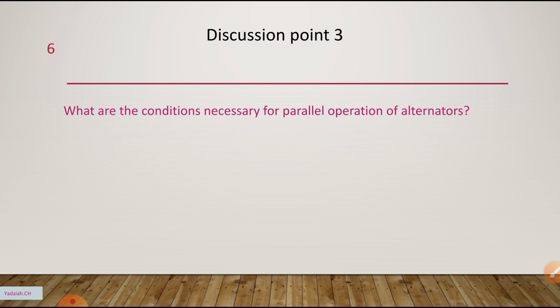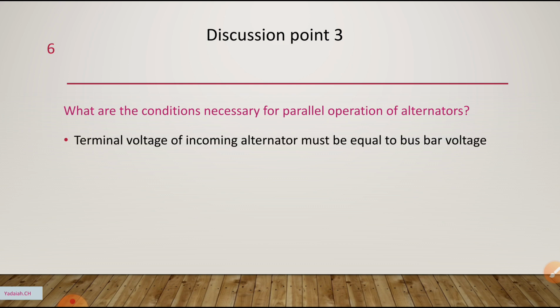One condition is that the terminal voltage of the incoming alternator must be equal to the bus bar voltage. That means, suppose the already existing alternator voltage is, for example, 11 kV, then the incoming alternator's terminal voltage should also be 11 kV. It should not be 9 kV, and it should not be 12 kV.